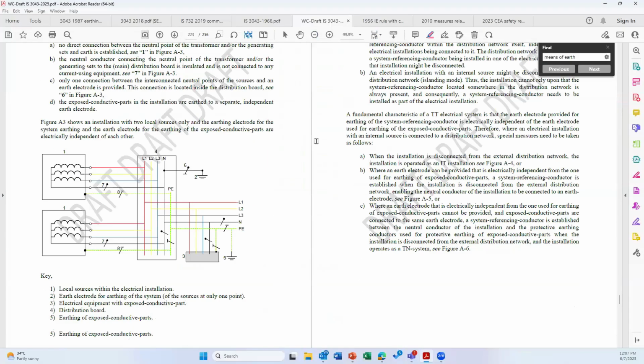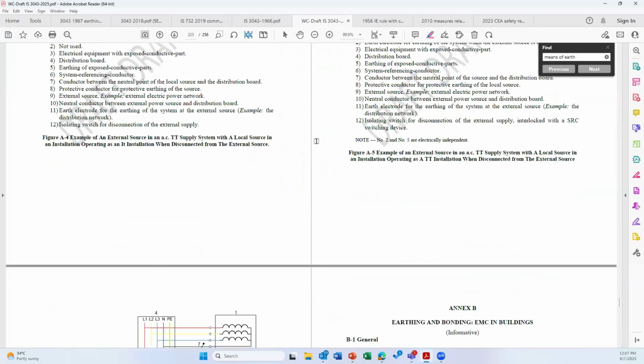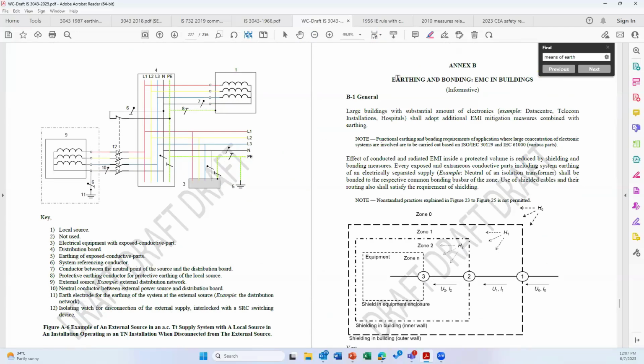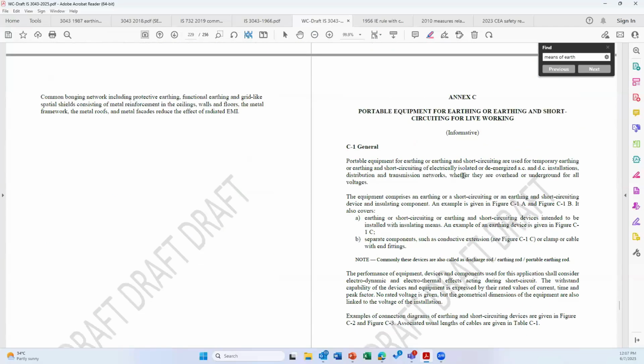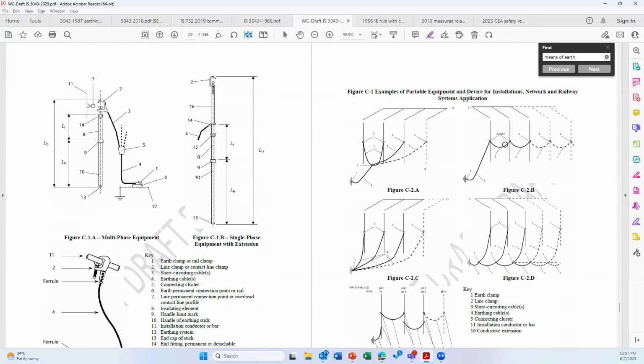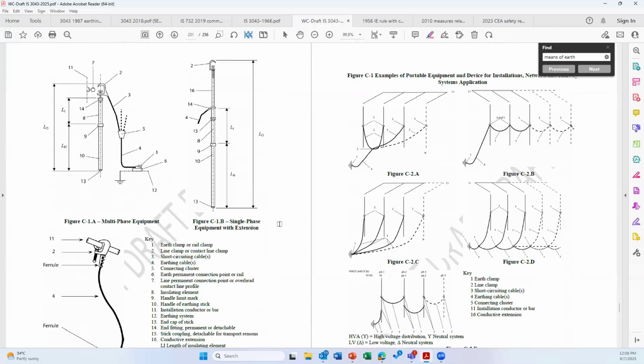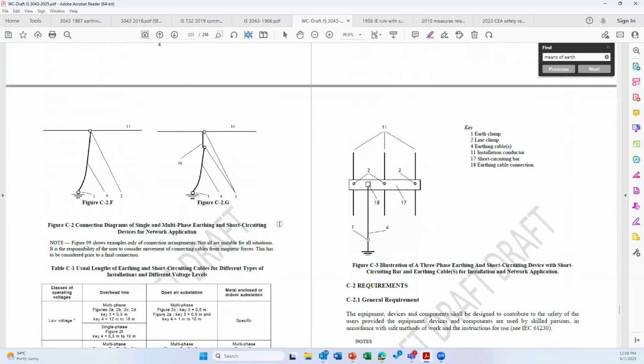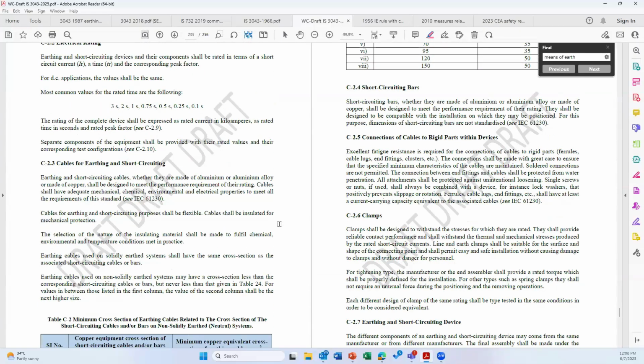These informations are included in the standard. Then earthing and bonding in and EMC in building, some small informations are being given. Portable equipment for earthing or earthing and short circuiting for live working. If you have a live line, how to make the earthing of the overhead conductors before jumping or before making a maintenance. These informations are taken from the IS standard and are being included.